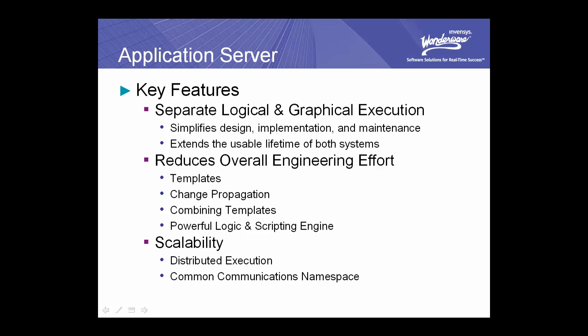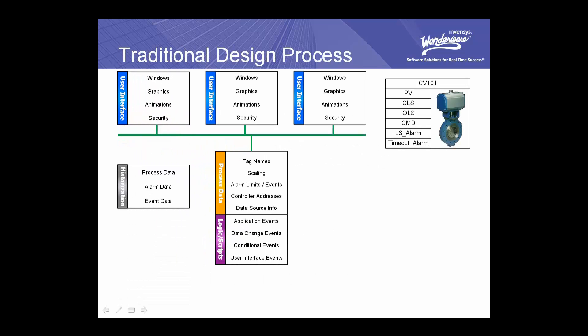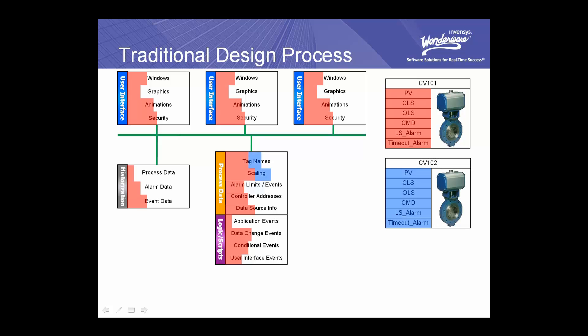You might be wondering, how is it simpler if I have two different systems to maintain? With traditional HMIs, where the supervisory elements and the visual elements were defined within a single application, you had numerous areas where you had to define all kinds of things. For any one device, like a valve, you would create multiple data point definitions — oftentimes called tags. Then you would go somewhere else to create scripts or logical elements that evaluate I/O bits and words, set calculated values, and things like that. Then you'd create windows, graphics, and animate those graphics. Eventually, you might even go to the historian and recreate the data points you'd already defined in your HMI. And when you added another valve, you'd do it all over again, creating each of these elements by hand.